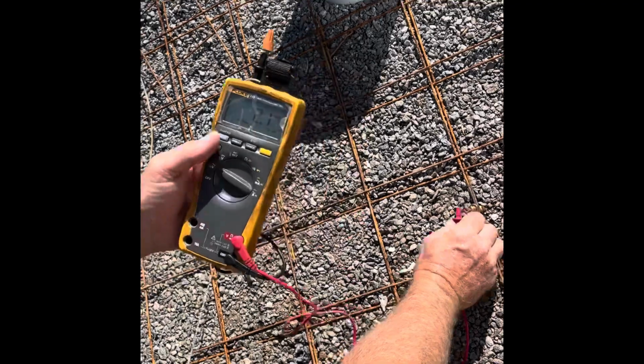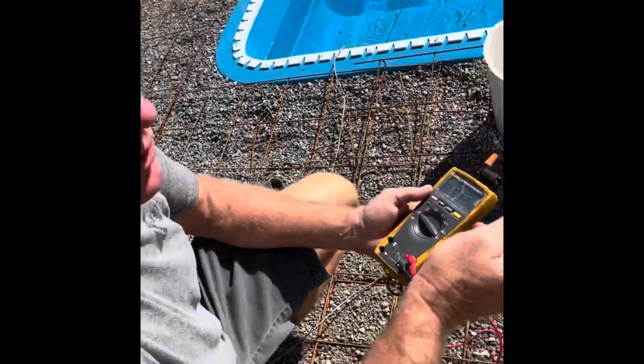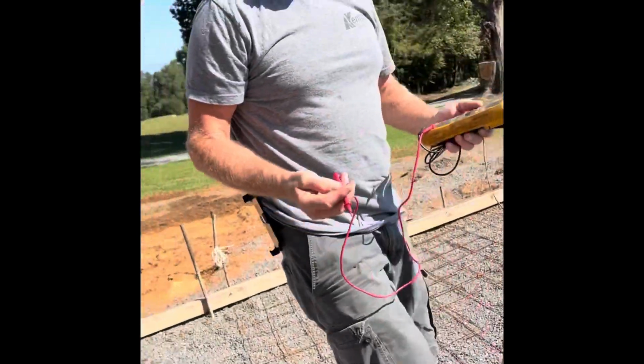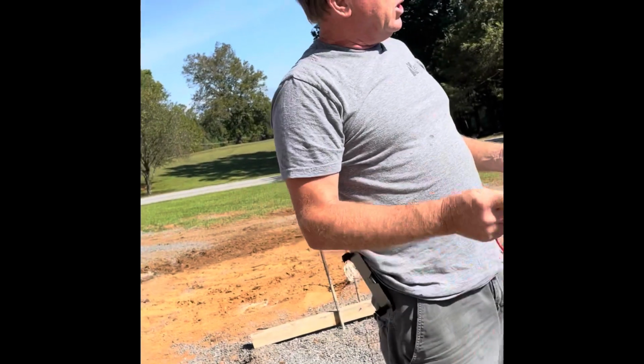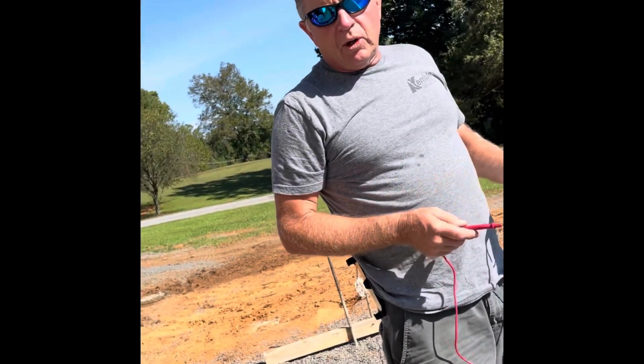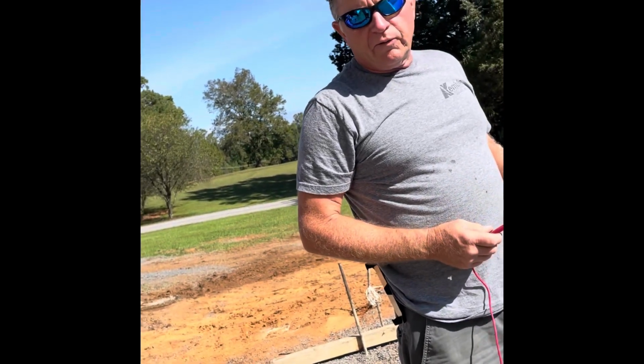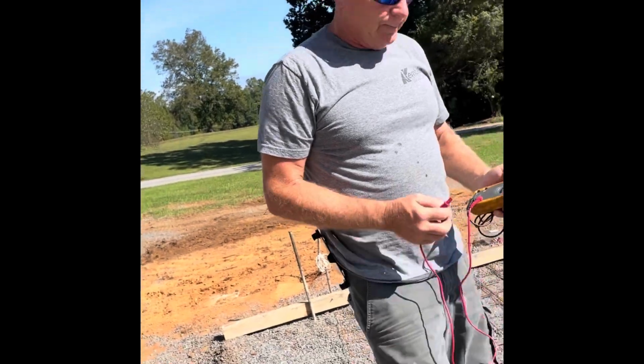So now what we're going to do is go all the way around the pool, check each one of those. All of that should come out to be the same reading. Then we're going to go out here, put a probe into the earth. We're going to do a neutral earth voltage test on this grid next.